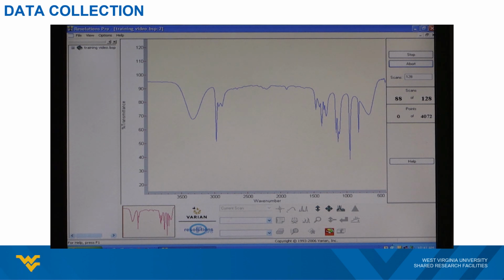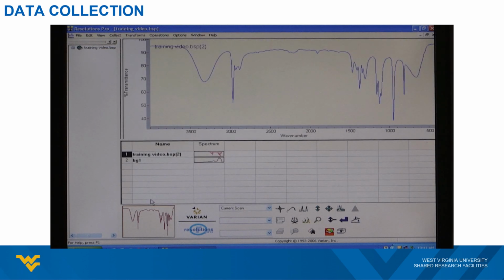Note that this spectrum is the final result after comparison with the background collected earlier. Once the measurement is completed, the software will return you to the main interface again, where you can assign a file name for the measurement. Following this, you can open the sample clamp and clean both the window and the tip using wipes and IPA. The system is now ready for the subsequent measurements.